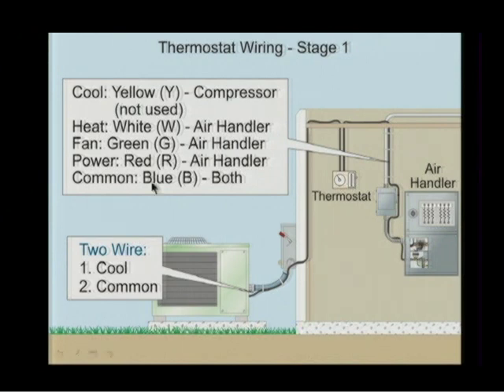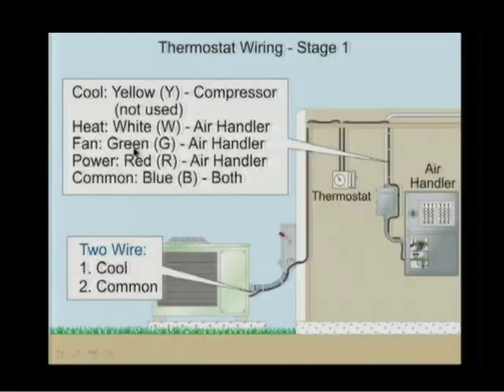The practice is, let's just assume we're running a raceway for convenience, and we're pulling our conductors, and we are going to color code the conductors. Are you with me? So we have control of color. If that's the case, yellow is for cool. That's the compressor. I would run a yellow wire over to one side of the relay, and the other side of the relay, I will then take a common conductor, and I'm going to use the color blue. So the common conductor comes back.